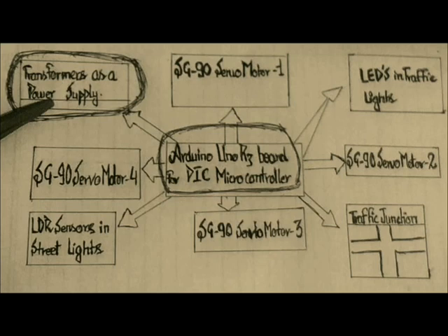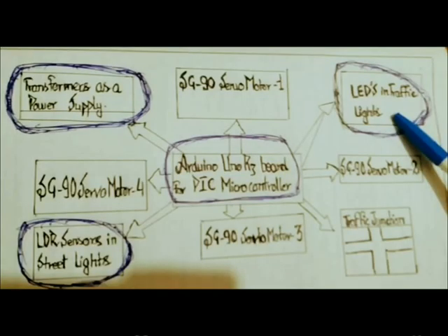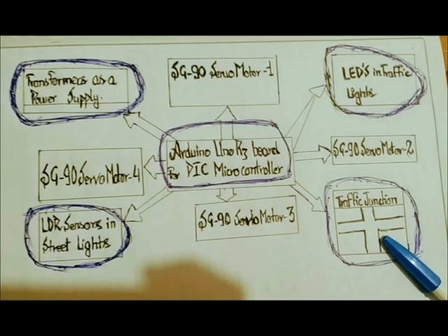For programming of street lights, we are using LDR sensors — that's Light Dependent Resistors — used for controlling automatic street lights. When light falls on the LDR, the voltage varies accordingly. So when sunlight is present, the street lights will be off, and when there is no light or during night time, the street lights will turn on automatically.